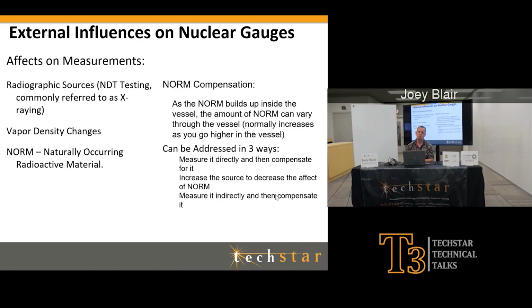Same is true if my vapor space has changed, and now I'm running a less dense vapor space than I used to, or a more dense vapor space than I used to. Then you would use that standardization. On some gauges, they call it real value correction. Just about every gauge, regardless of the manufacturer, is going to have some sort of name for it, but it's a single point calibration. That would probably be one of the most common inaccuracies.